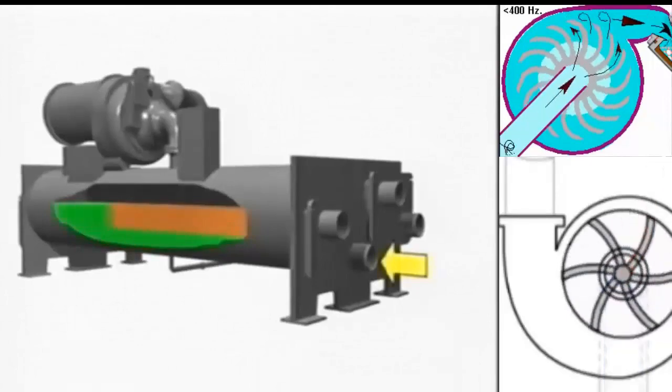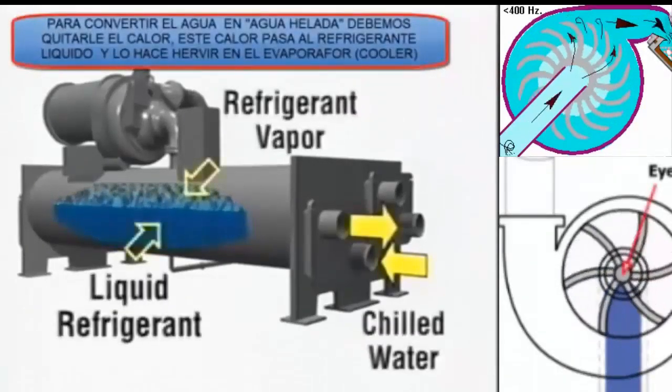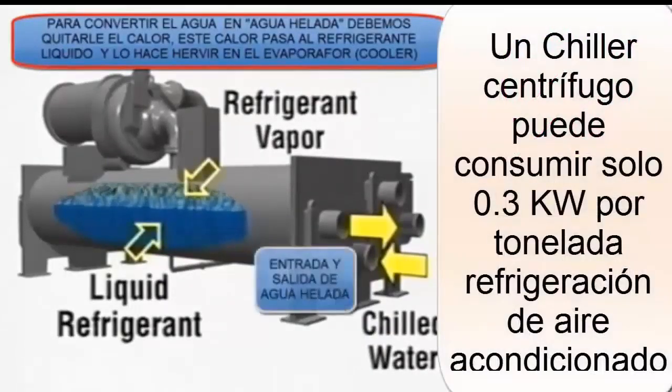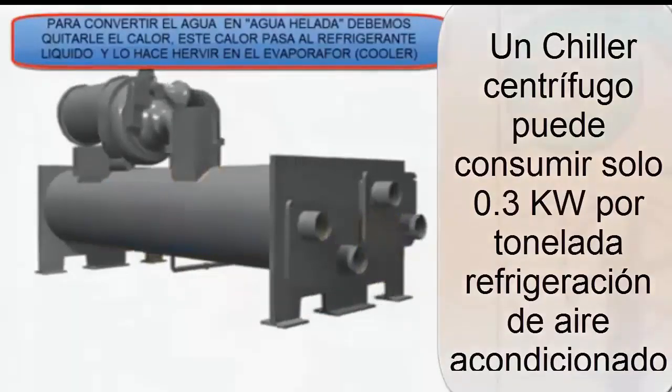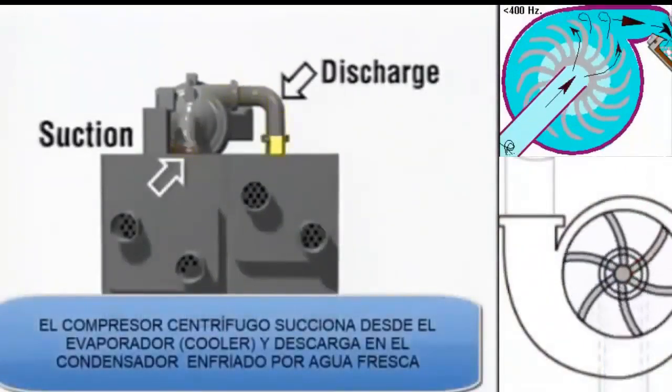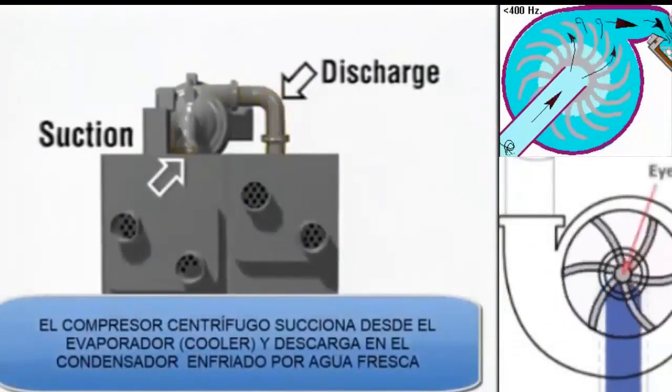The chillers with centrifugal compressor are chillers that acquire a very high efficiency. We are going to relate from 0.3 kilowatts for each ton of refrigeration. We are going to consume half of what a conventional air conditioner consumes, one of those that already come with high efficiencies, with inverter equipment, it can even achieve half of that consumption. That is why large air conditioning plants are looking for the chiller with centrifugal compressor.